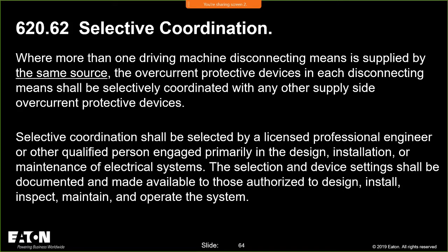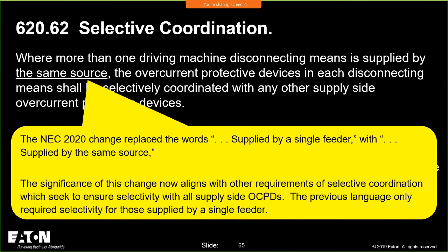Now the code changed this. See where it says, where more than one driving machine disconnecting means is supplied by the same source. That used to say supplied by a single feeder. The significance of the change is that it aligns with other areas in the NEC where selective coordination is required, and it moves its way back up to all overcurrent protective devices on the supply side. The previous language only required selectivity for those supplied by a single feeder. Now it covers multiple feeders.